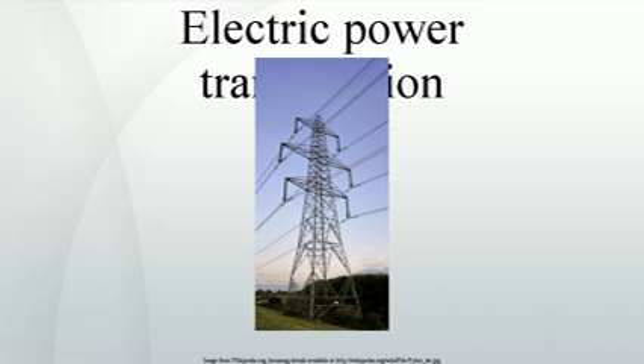Underground transmission. Electric power can also be transmitted by underground power cables instead of overhead power lines. Underground cables take up less right-of-way than overhead lines, have lower visibility, and are less affected by bad weather. However, costs of insulated cable and excavation are much higher than overhead construction. Faults in buried transmission lines take longer to locate and repair.